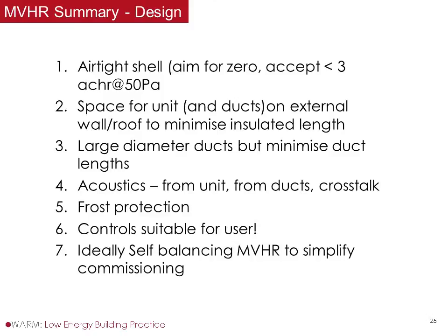Control suitable for the user — we talked about this, and it's a relatively new thing. In terms of commissioning, our advice is very strong now. We don't believe MVHRs get commissioned properly in this country, and we're now suggesting quite strongly that you get an MVHR that's self-balancing within a certain range, meaning it will alter the airflow through one side, say the extract, to match that through the supply.